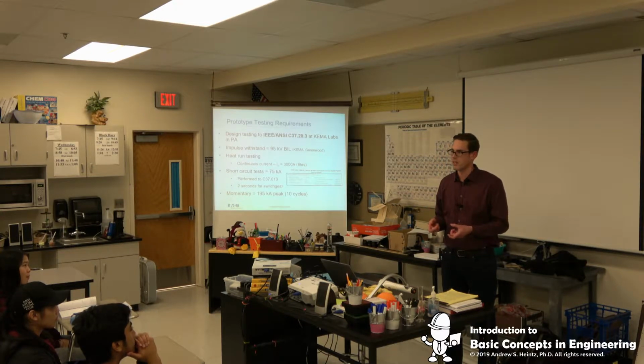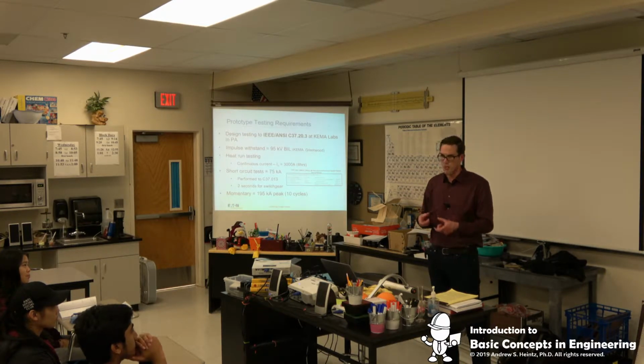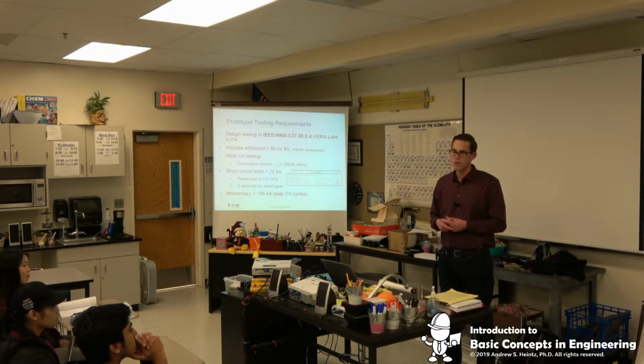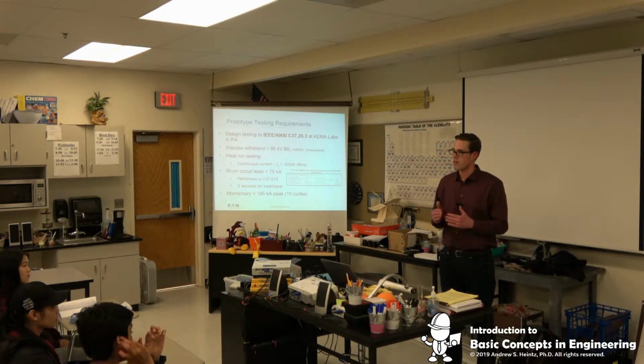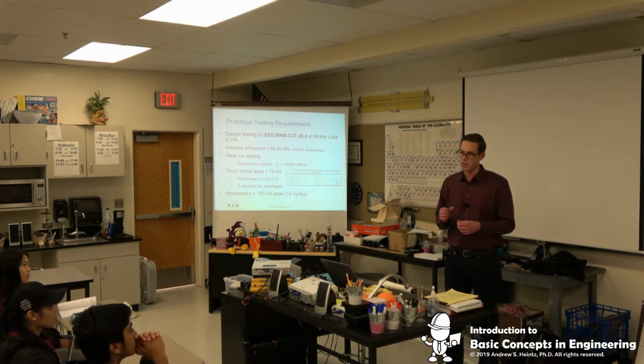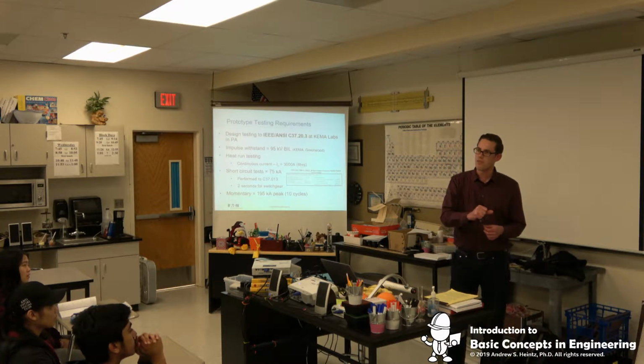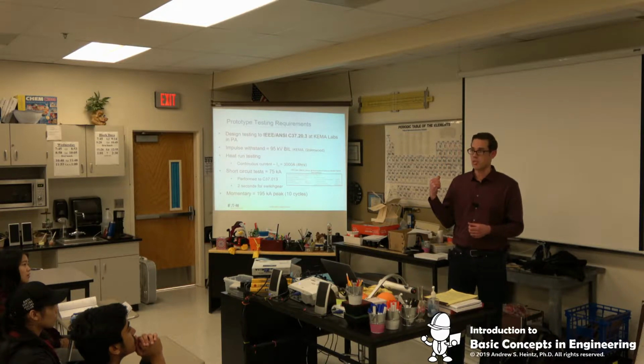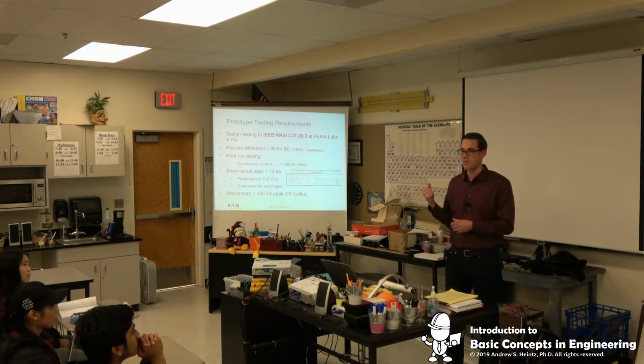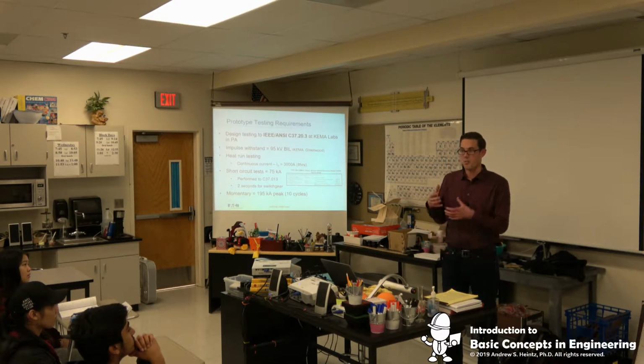basically a microprocessor programmed with specific trip levels and communications. So all circuit breakers work a little differently, but in a straightforward fashion they're all monitoring the amount of current flowing through the load, and in some way you're releasing mechanical energy. The breaker in your house, when you turn it on, you can feel the resistance - you're charging a spring. Same thing with that breaker, except the springs are much, much bigger, because that's, like we said, 200,000 amps. It needs a ton of energy to physically open that device.